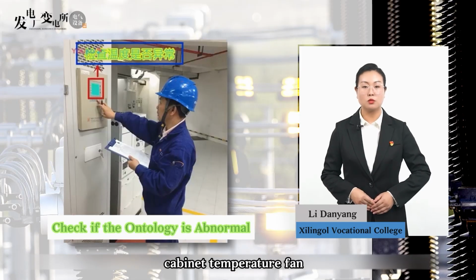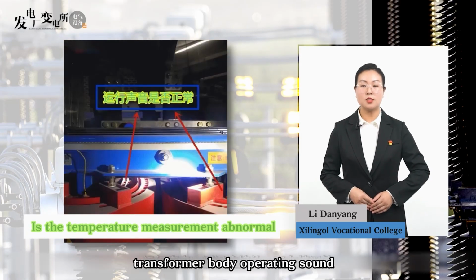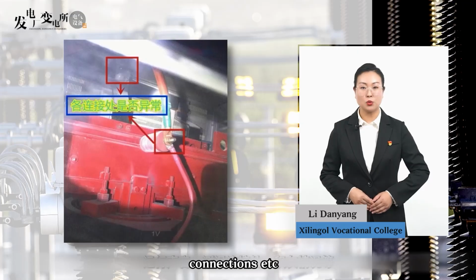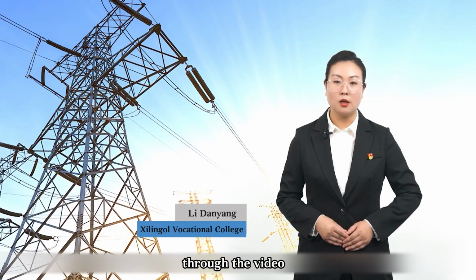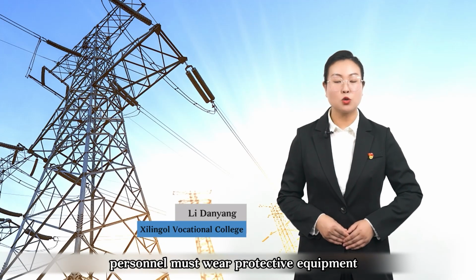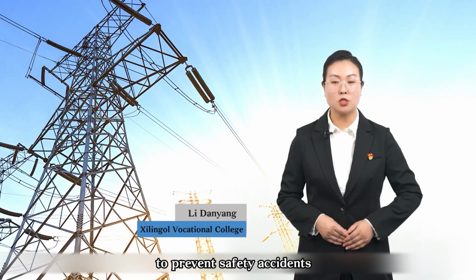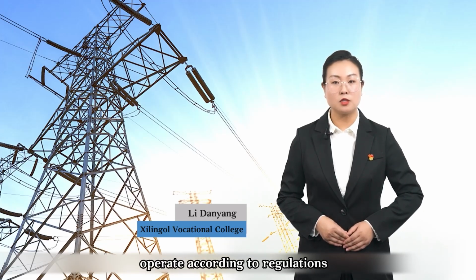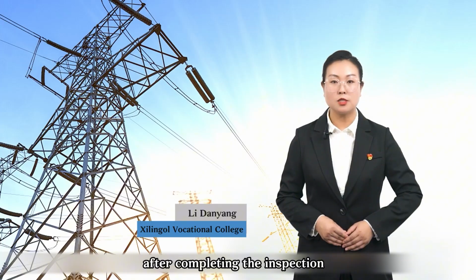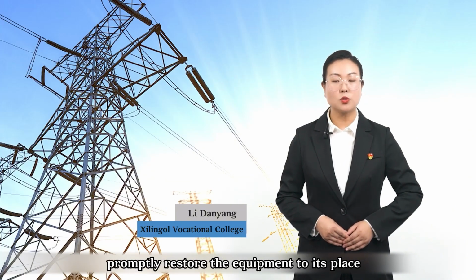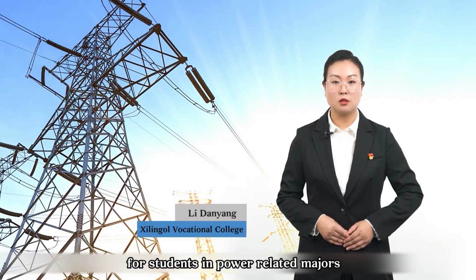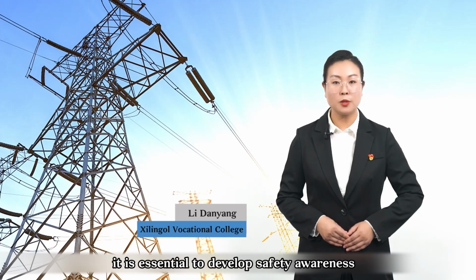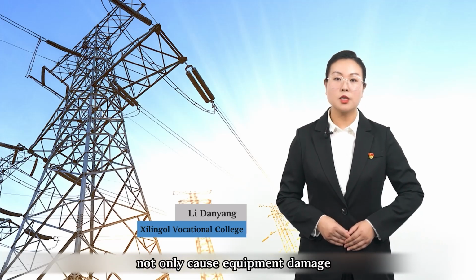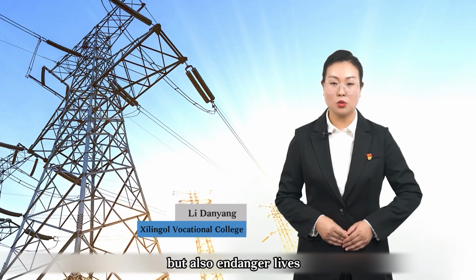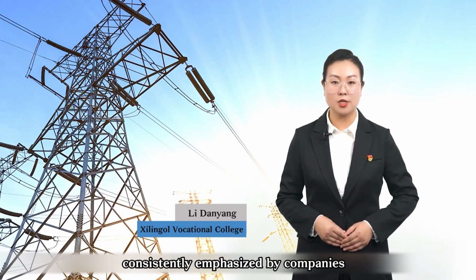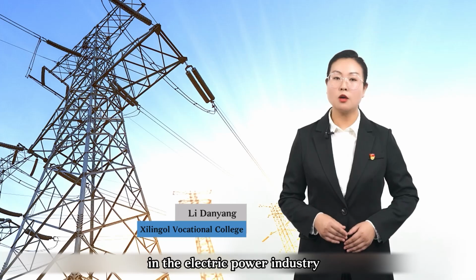Cabinet temperature, fan, transformer body operating sound, dust accumulation at temperature measurement connections, etc. Through the video, we found that on-site inspection personnel must wear protective equipment to prevent safety accidents. After arriving at the site, operate according to regulations. After completing the inspection, promptly restore the equipment to its place. For students in power-related majors, it is essential to develop safety awareness, because power accidents can not only cause equipment damage but also endanger lives. This has also been a safety competency consistently emphasized by companies in the electric power industry.